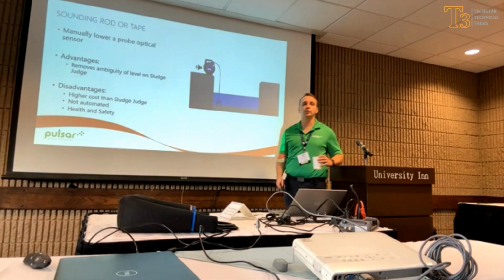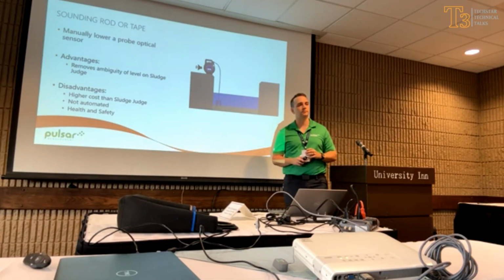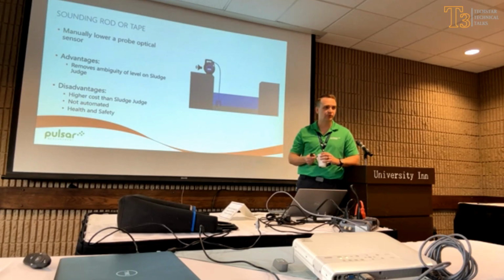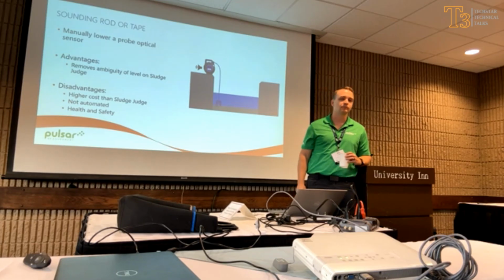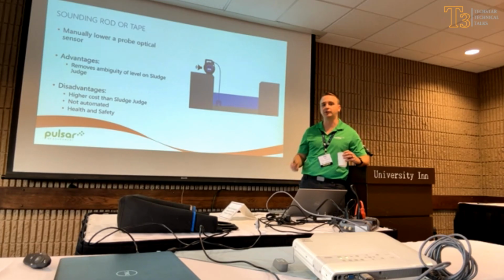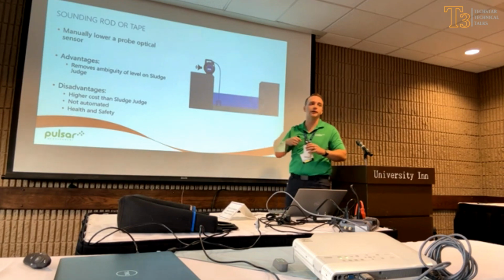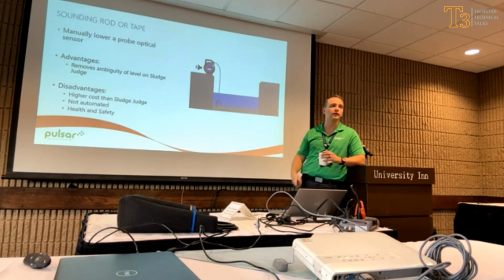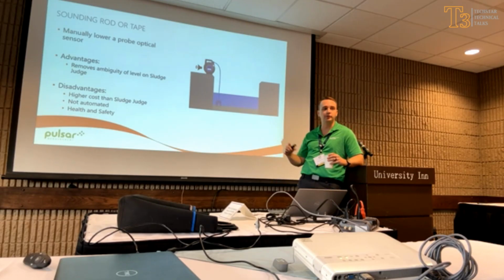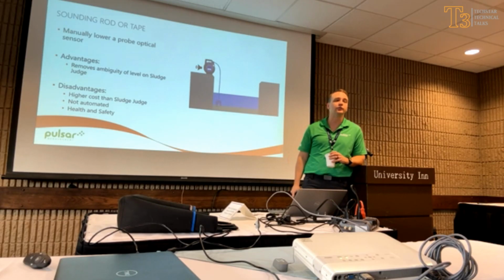Okay, another point level device. Has anybody seen an optical style tape sensor? Anybody use something like that? Mr. Casey has? Okay, so these are very similar to a sludge judge, but the idea is that you want to take the manual variance out of it, depending on how fast you inserted it and took it back out. Essentially this is a probe on the end of a spool rod, and as you let it out, it takes a measurement of the density of the solids. It's designed to remove that ambiguity, that uncertainty of, oh man, was it like 3 feet, was it 2.5, depending on how the operator is inserting it.